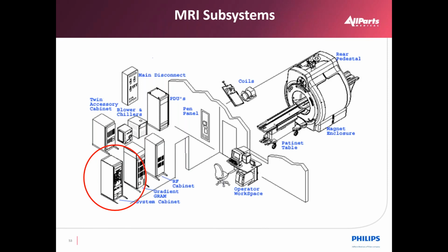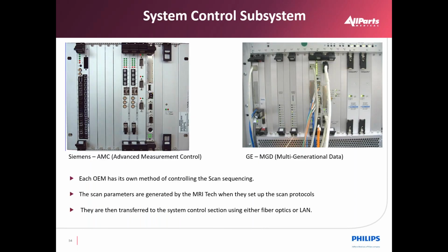The components in the system control section are used to manage the collection and processing of all the signal data from the scan. Each OEM also has its own method for controlling the scan sequencing. The parameters used for the scan are provided by the MRI tech when the scan protocol is set up. These parameters are transferred to the system control section either via LAN or fiber optics.